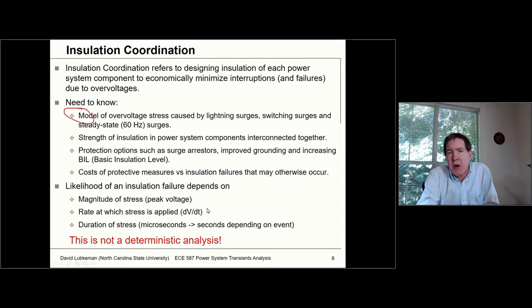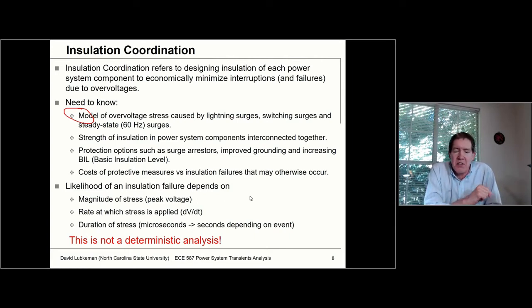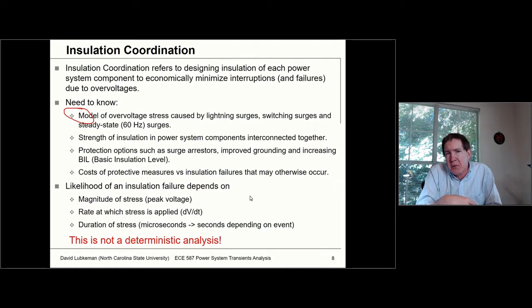We also need to know the rate at which the stress is applied because insulation is sensitive to dV/dt, and also how long the overvoltage will occur. Insulation coordination calculations are not deterministic — if I apply a stress to a component, it may fail or it may not. It's very dependent on ambient conditions and how many loose electrons are around. It's very probabilistic in nature, which is why we use probabilistic techniques and Monte Carlo simulation in programs like PSCAD, assigning a probability density function to things like point-of-wave switching.